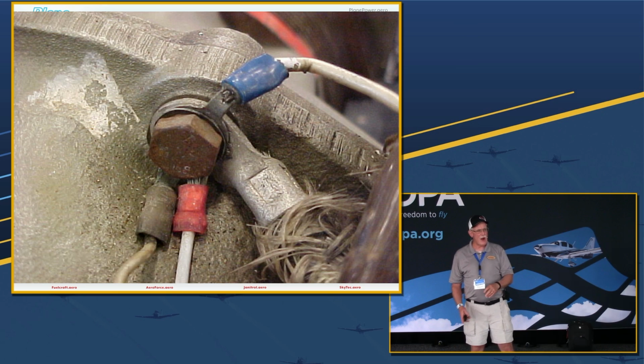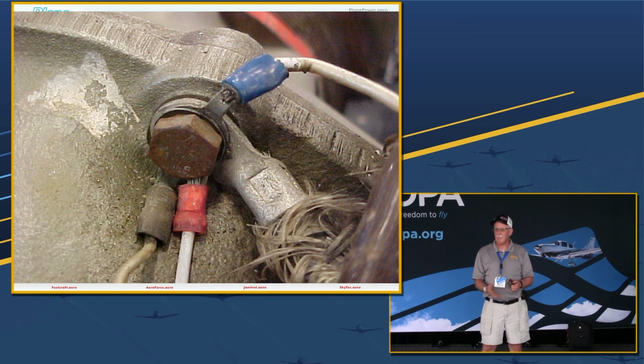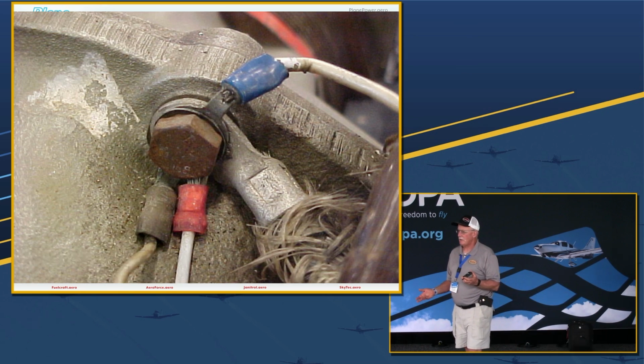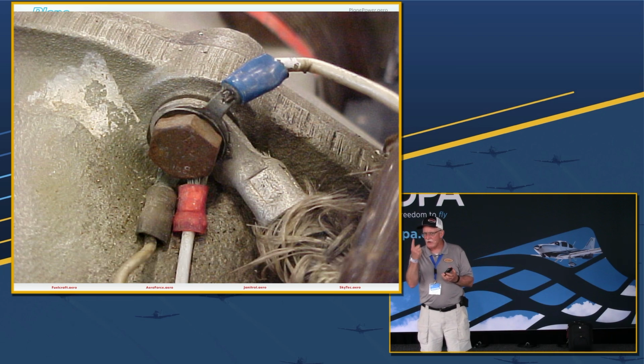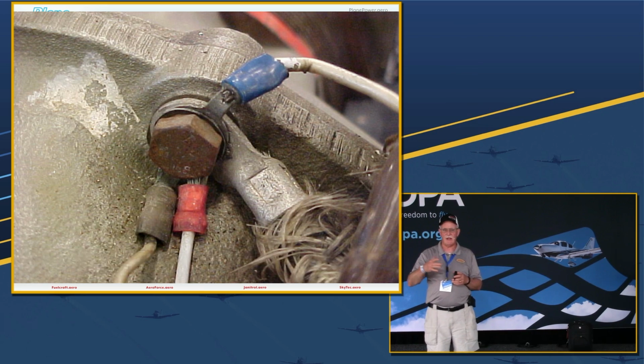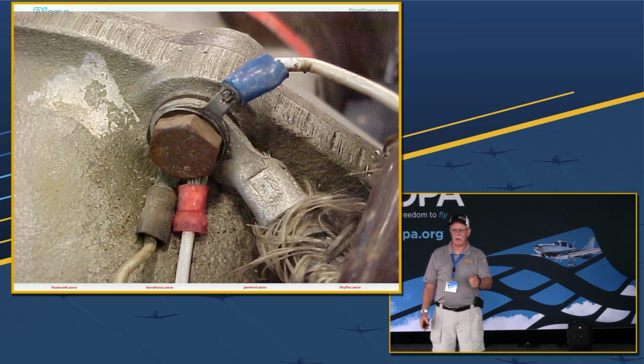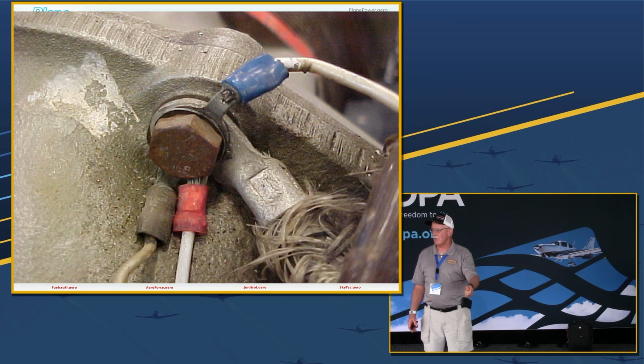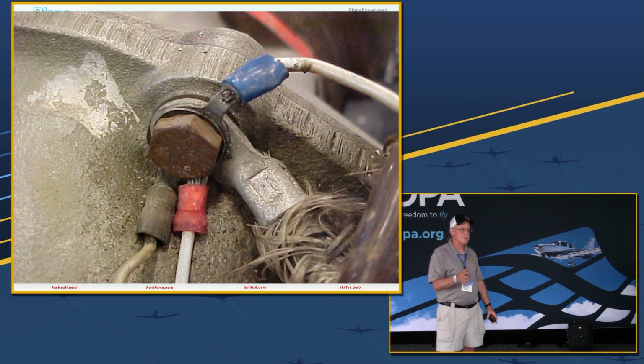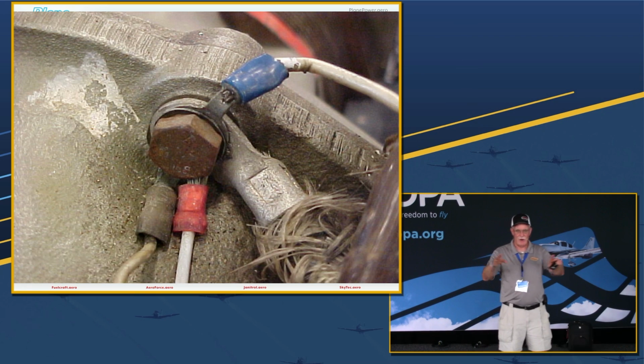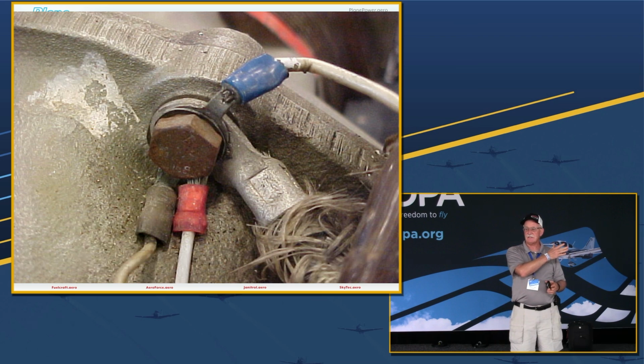Those other ones - why do we have so many on one spot? How many grounds do you actually need? You need one ground. You don't need everybody that put a piece of equipment on this airplane over the last 20 years saying 'well I got to wire it, I got to put a ground on' - they put another one on, and another one on. What happens is you get a split where you split the grounds, and electrically it looks at it and says, using our Ohm's law formula, we're going to split this parallel path up and split all that resistance at the same time.